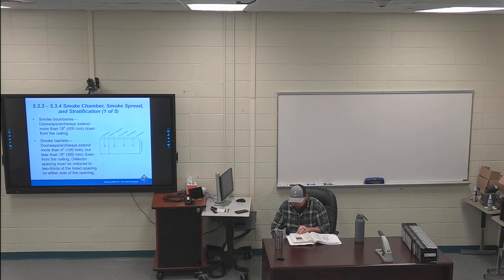Moving on to page 50 and 51. 535 talks about smoke detector installations on flat or smooth ceilings. I've got nothing highlighted. Like, they talk about how you're supposed to set up these different types of detectors and what rooms and ceilings that have pan ceilings and stuff like that. You're going to have different types of detectors that go into that. So wouldn't be a bad idea to read through these different sections.